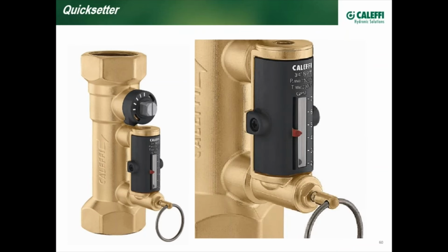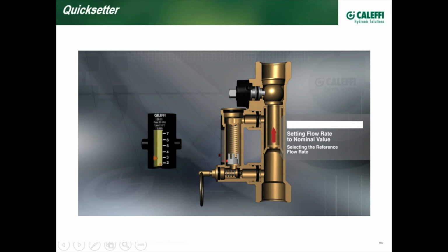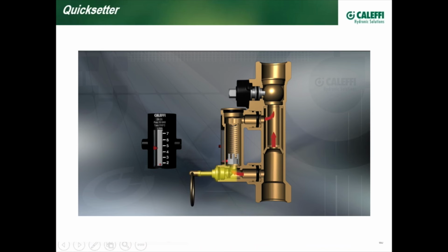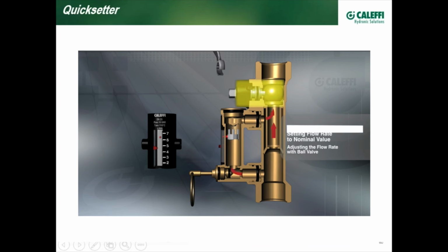Caleffi solved that problem of static balancing valves by putting the gauge right on the valve itself, called Quick Setter. Here you see a photo of it. Flow would go up like the arrow shows here. When it comes time to set the flow rate on the circuit that the valve is placed in, the contractor pulls this pin. By doing so, some flow bypasses through this loop here by way of an internal venturi. As fluid goes up this center section here, inside of here is a magnetic disc attached to a spring. The disc rises up in the stream of the fluid, and the magnetic disc attracts a ferrous bead on the outside of the valve itself. As it rises up, it indicates the gallons per minute going through the valve.